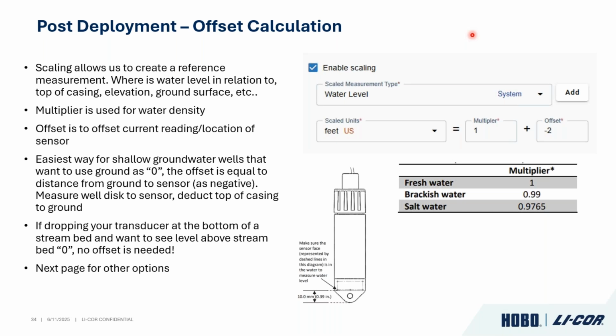I mentioned in the beginning, if you are doing shallow groundwater wells, there are a lot of wetland restoration projects utilizing this equipment. If you were able to take a measurement from your well casing to the bottom of the sensor, and you want to see ground as 0 and anything below it as a negative number, so as that water level rises and gets to ground, it shows as 0. If it's above ground, it's a positive number. If you want to see it that way, really all you need to punch in, if this section of the transducer is 2 feet below ground surface and ground is 0, is an offset of -2. So that's one way to do that for shallow groundwater wells.